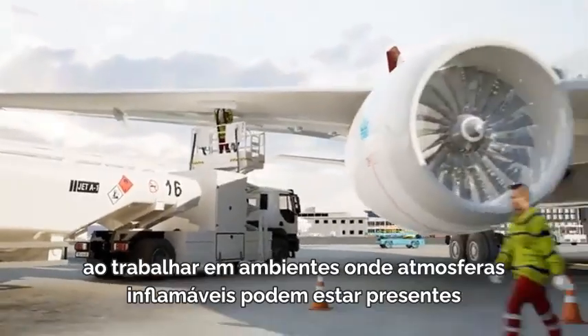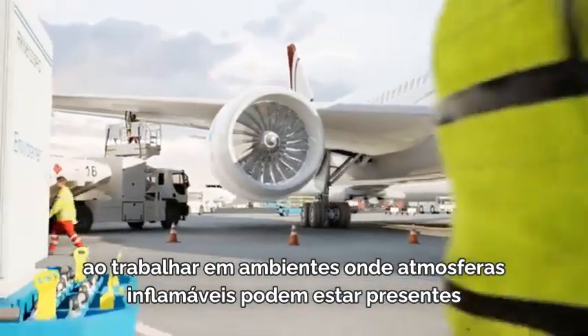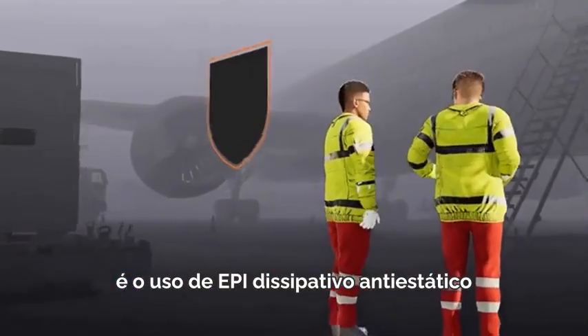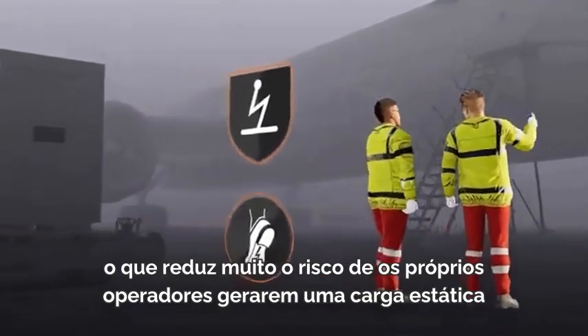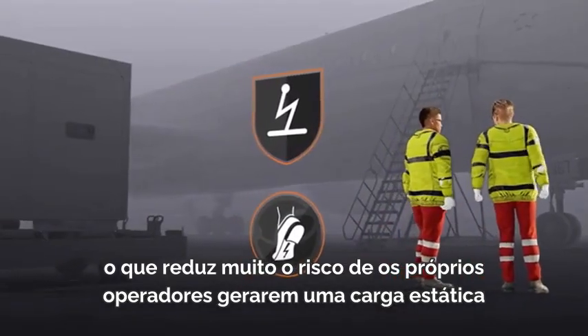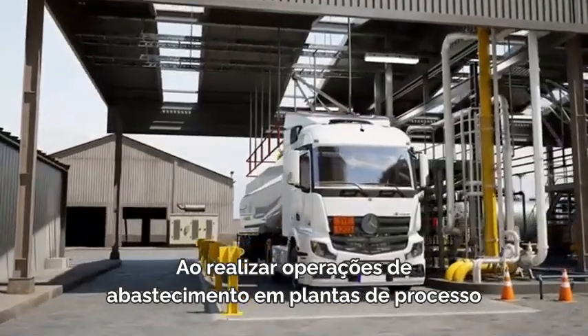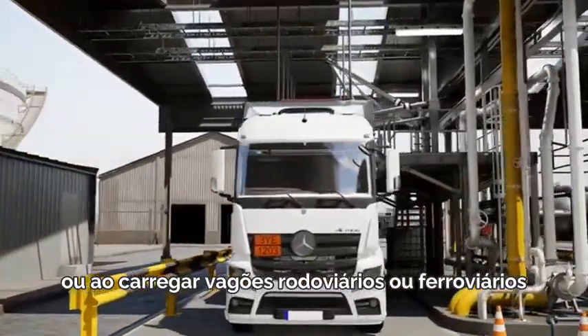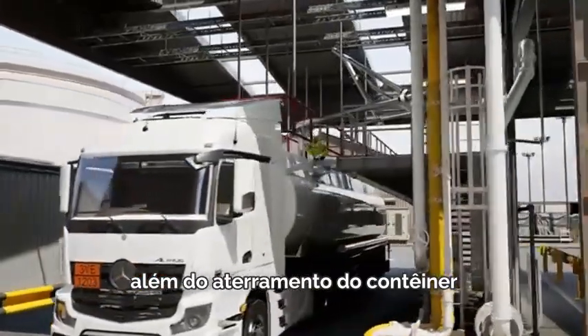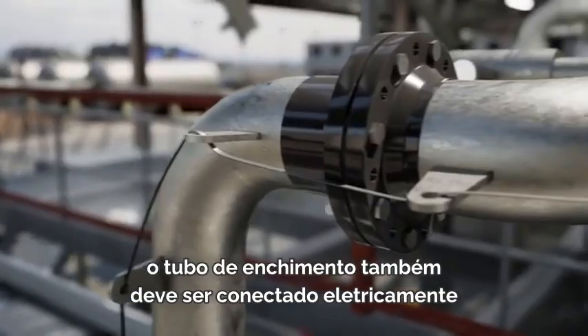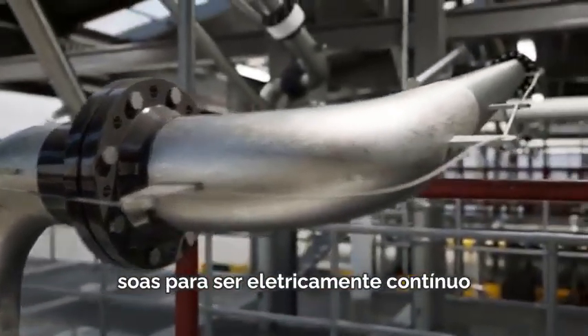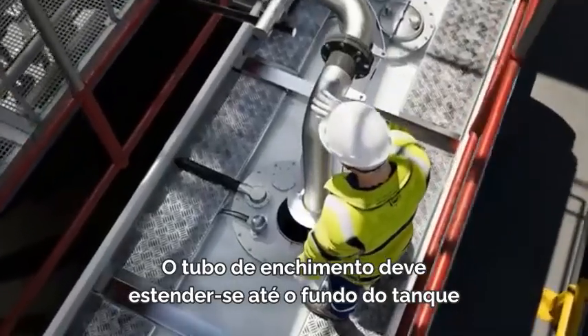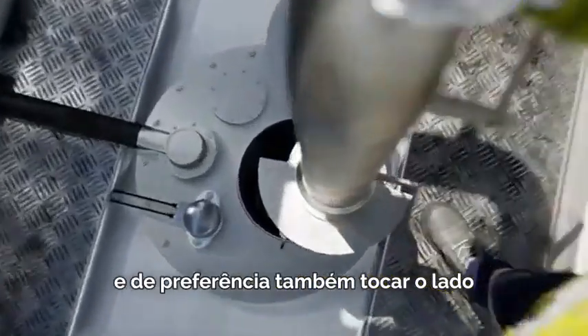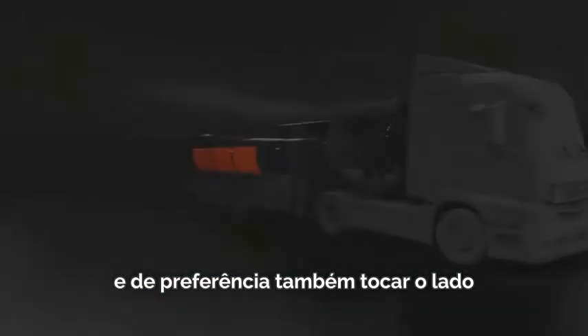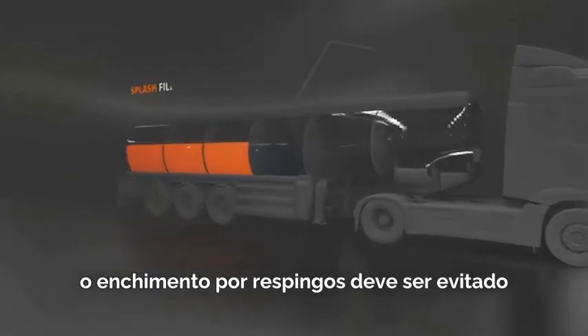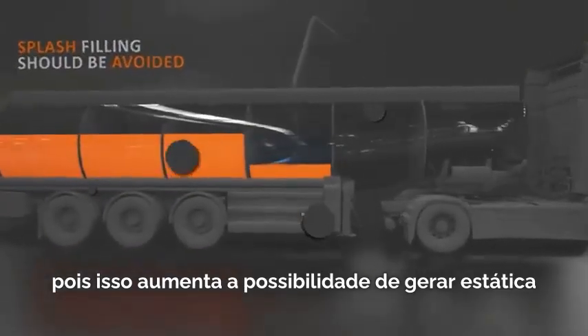A basic control measure when working in environments where flammable atmospheres may be present is the wearing of anti-static dissipative PPE, including footwear, which greatly reduces the risk of operatives themselves generating a static charge. When conducting bunkering operations on process plant or when top-loading road or rail cars, in addition to the container being earthed, the fill pipe should also be bonded electrically to earth, with all the assembly bonded so as to be electrically continuous. The fill pipe should extend to the bottom of the tank and preferably also touch the side. Irrespective of the product, splash filling should be avoided as this increases the possibility of generating static.